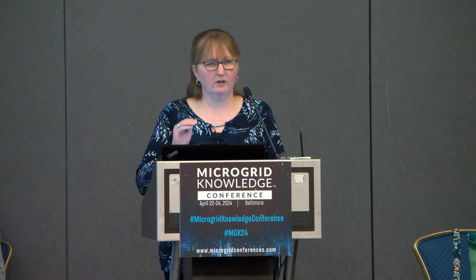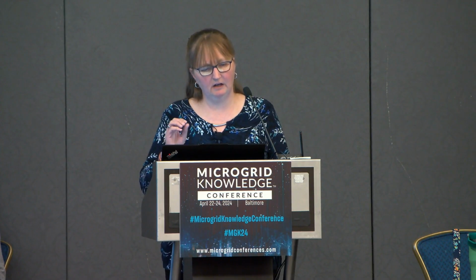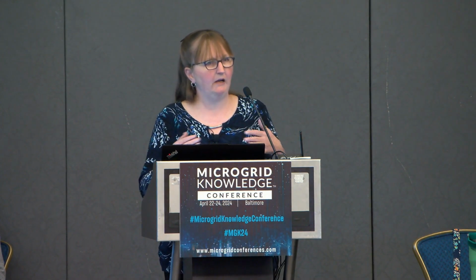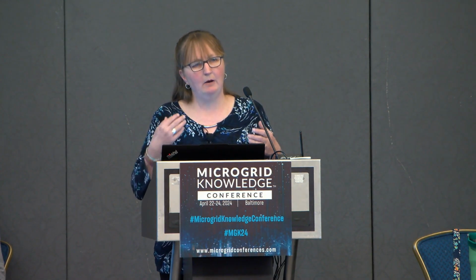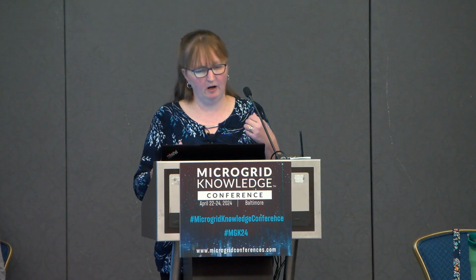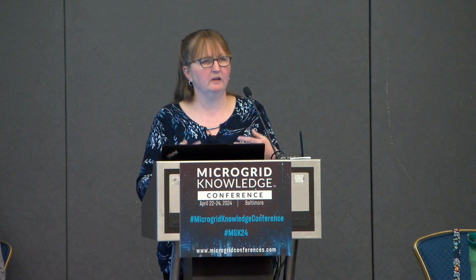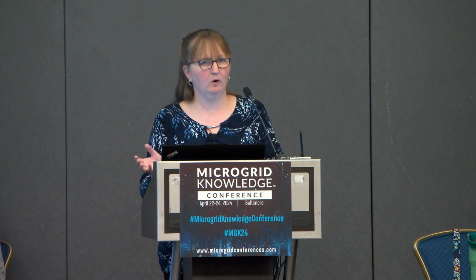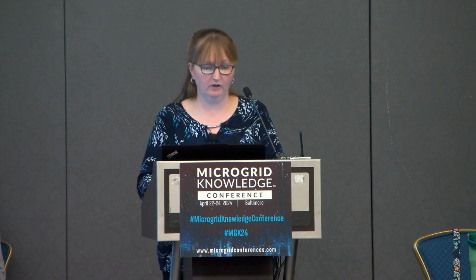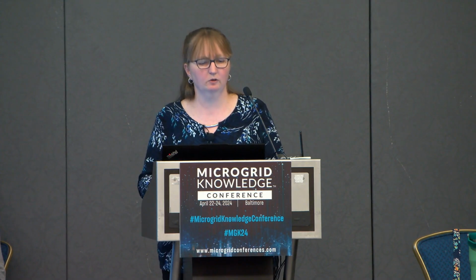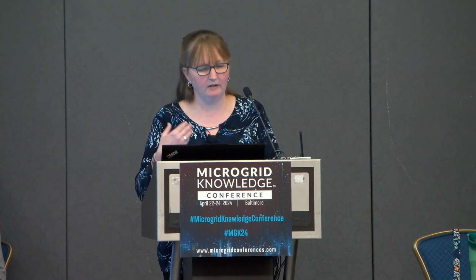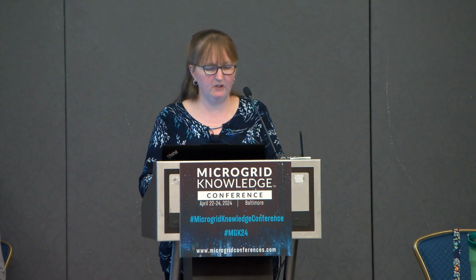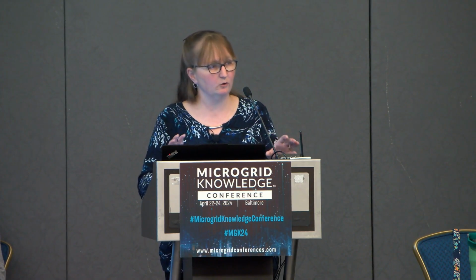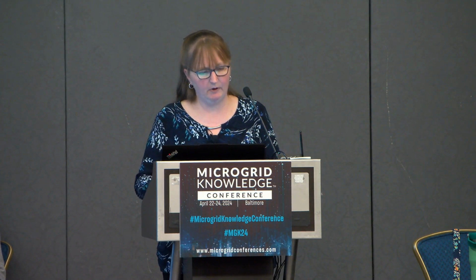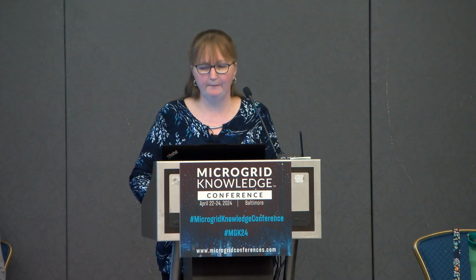Right now we're actually looking at possibly raising it to the full potential of the battery. We had to do some testing to figure out how much solar we can generate, how much of the PJM can we work with before we look at possibly overloading, feeding back. And it looks like we're going to be in good shape to fully run the solar at its full 2 megawatt capability, the full PJM, so 1 megawatt from each of those 2 batteries that I mentioned, and keep it going. And this will help our ROI.